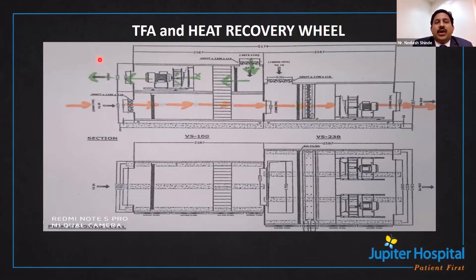Now if you see here, all our exhaust comes from here, and after heat recovery, which is always moving round the clock, it goes out from here. During winter we can have the advantage of passing the air directly. In summer, if fresh air is coming in at somewhere around 33 degrees, the heat recovery makes sure it comes down at least 4 degrees, to 29 degrees here. So instead of the 33 degree outside ambient temperature, this 29 degree air goes to the chilled water coil, which then has to work less because the temperature difference is 4 degrees lower, and that air goes into the wards. This is the treated fresh air and heat recovery wheel which we have utilized in our new project.